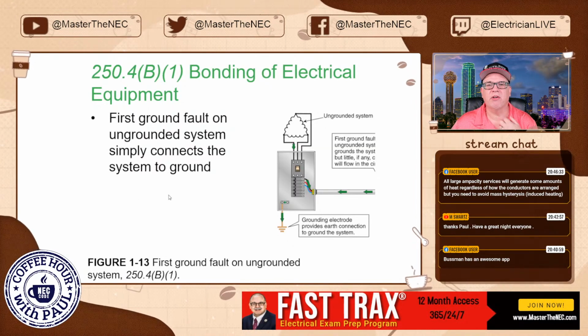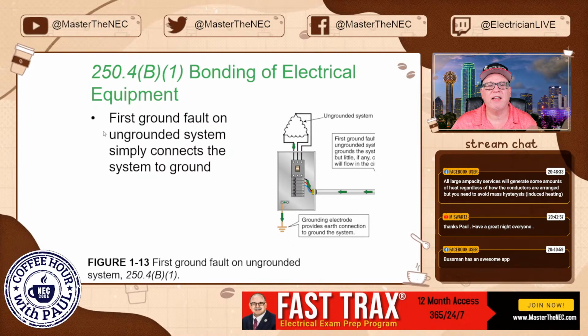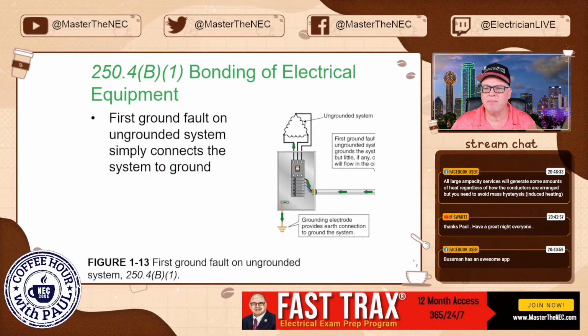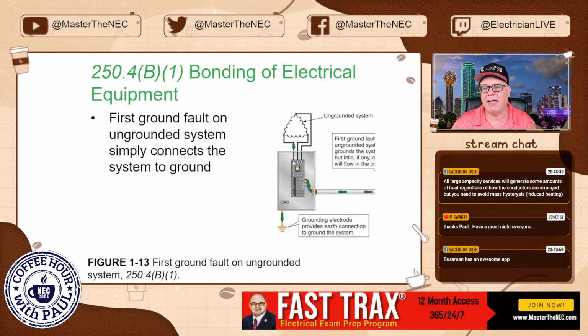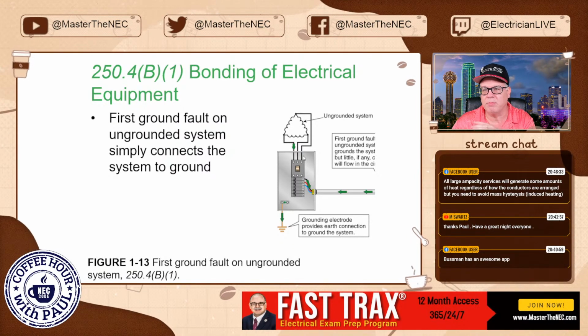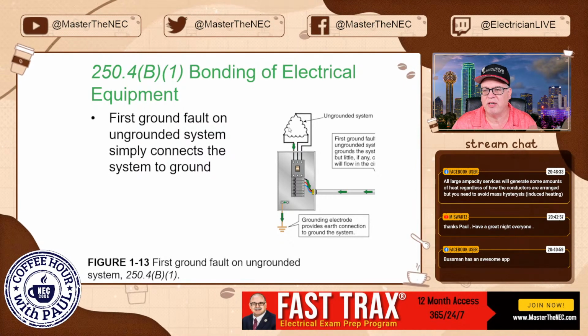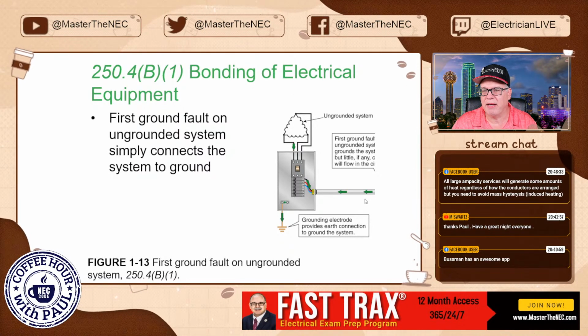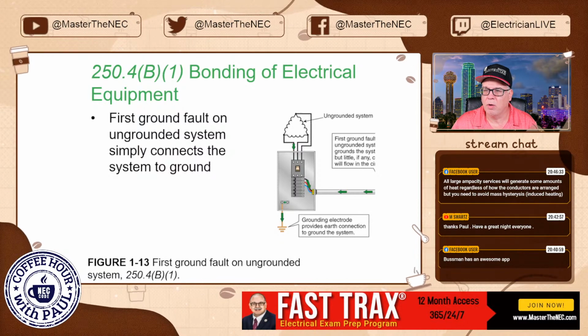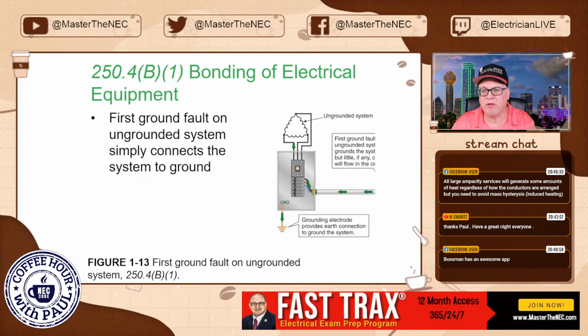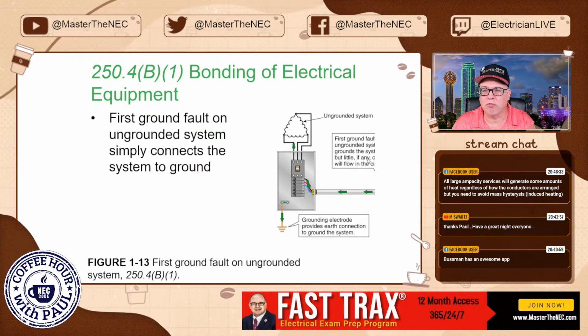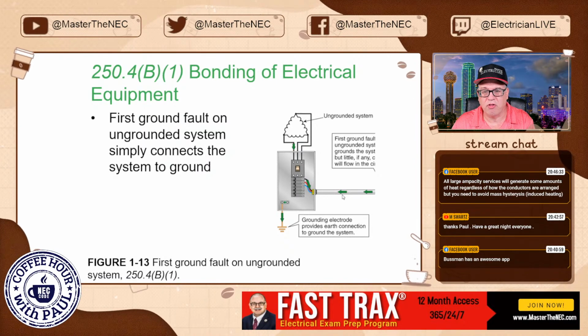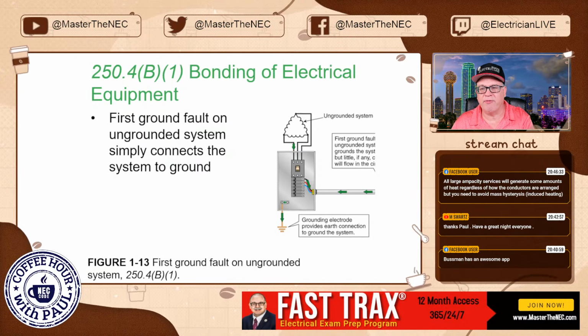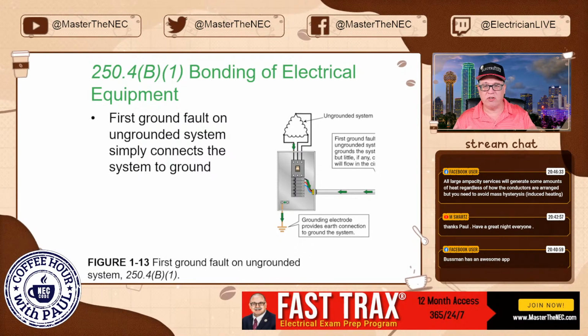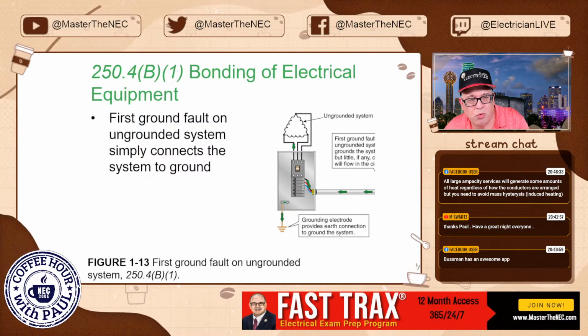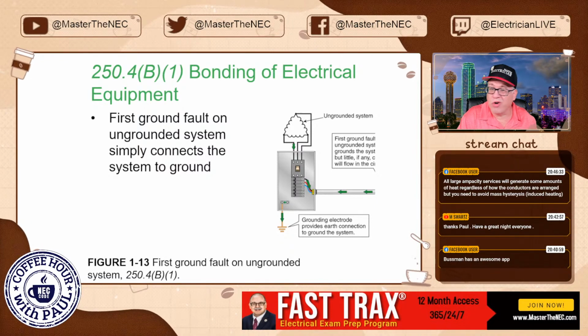So let's look at an example here. 250.4(B)(1), it says, this is an ungrounded system, okay? Wherever it's being supplied from here, it's coming in, 3 phases, boom, boom, boom. It's coming in, A, B, and C. Now here you see it going downstream, and we get a fault right here. The first ground fault on an ungrounded system grounds the system, okay? So in other words, it turns one of the phases. When you get a fault, if there's a phase fault here, what does it do? It turns this system into what? A corner grounded system.